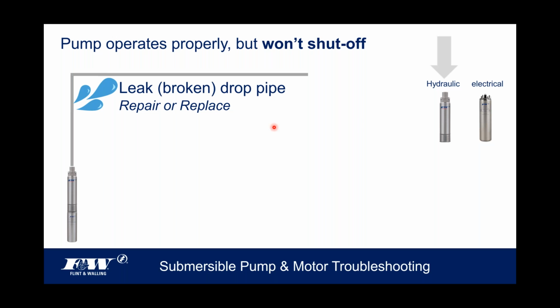That leak can be significant enough that it simply makes it impossible for the pump to build up the pressure it needs to satisfy the pressure switch and shut it off. So if that's the case, we want to look for that. Sometimes with a leak or broken pipe, you can look at a pressure gauge, if it's properly located. You can sometimes see that pressure drop, even while the pump's not running, because of the leak in that drop pipe.